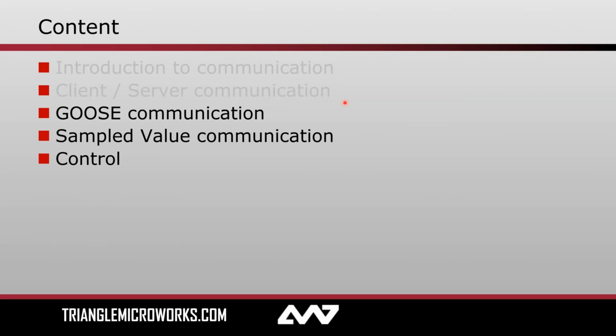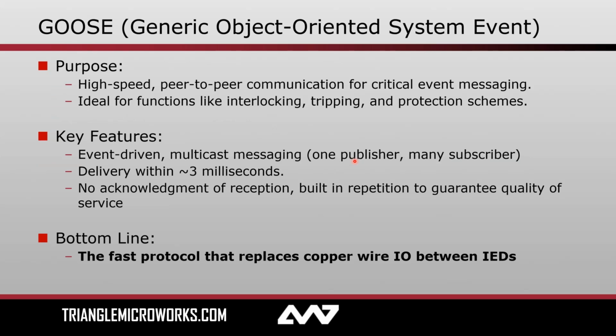All right, so now that we've spoken a little bit about client server, I want to go ahead and dive into the next communication protocol, which is going to be GOOSE. So we covered this a little bit, from a high level in our first webinar, but now we're going to be going a little bit deeper. So GOOSE stands for Generic Object Oriented System Event. Sometimes you'll hear that S as substation. It has officially changed as part of the standard and now stands for system. And that's as 61850 applies to more and more applications outside of just traditional substations.